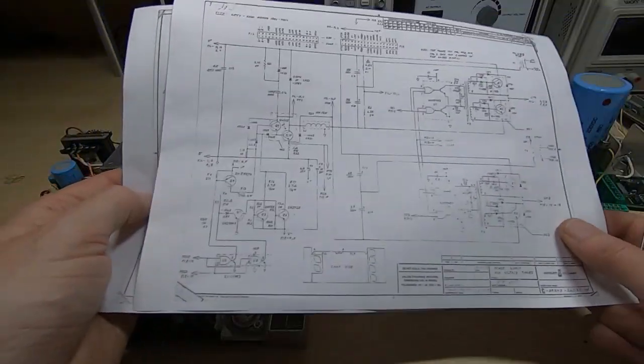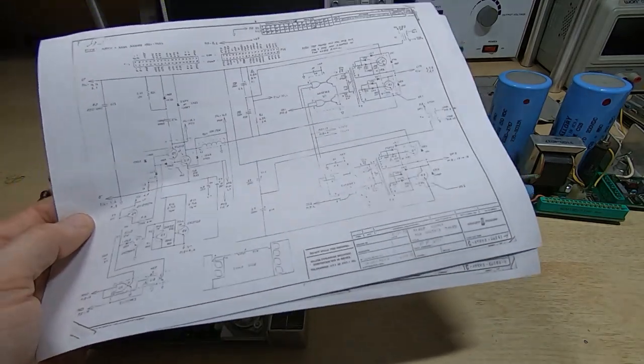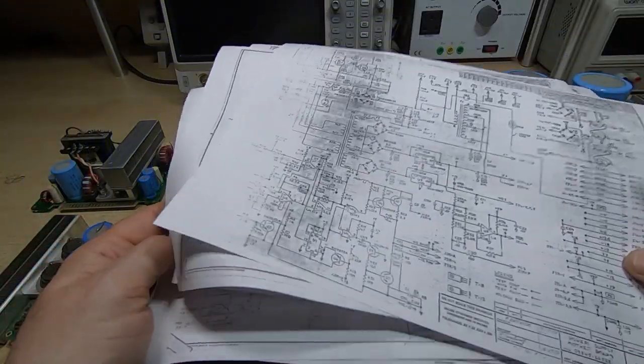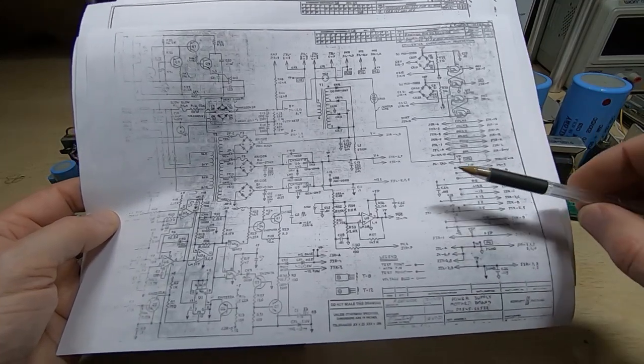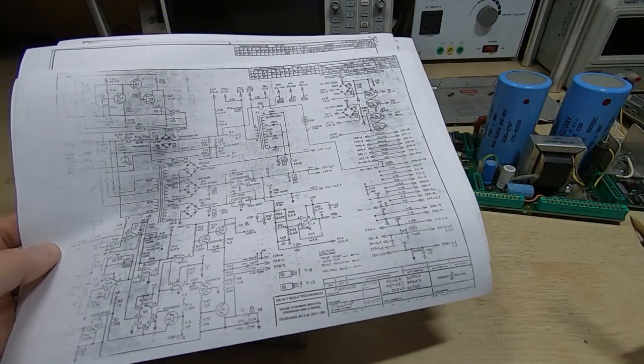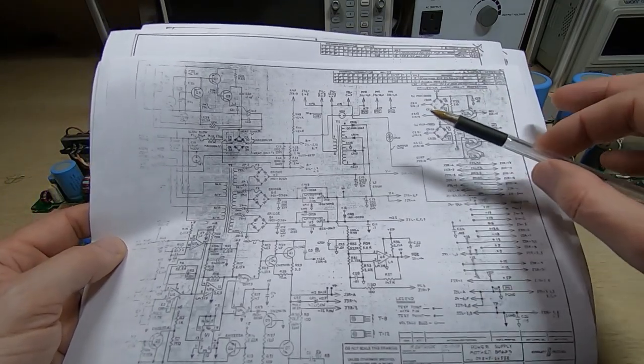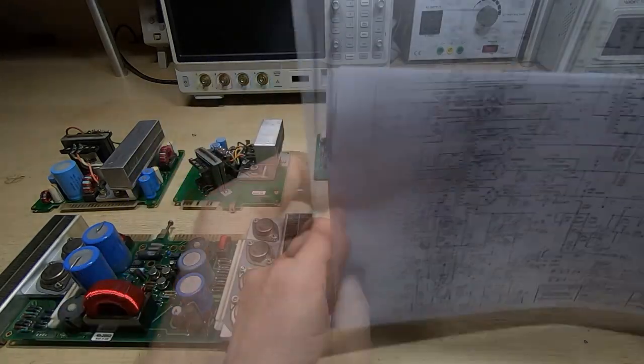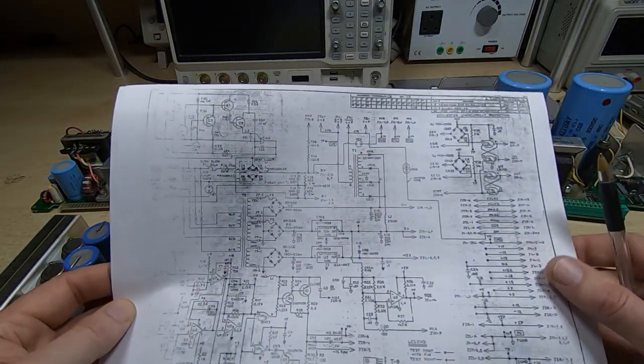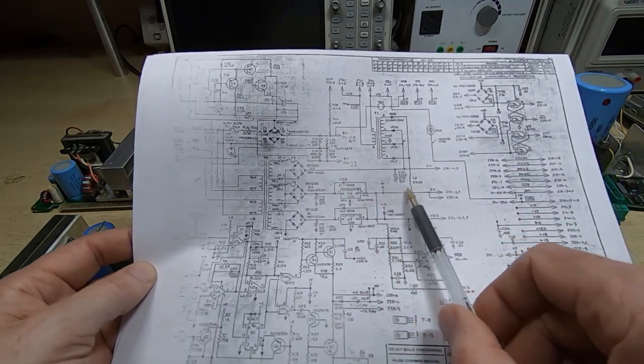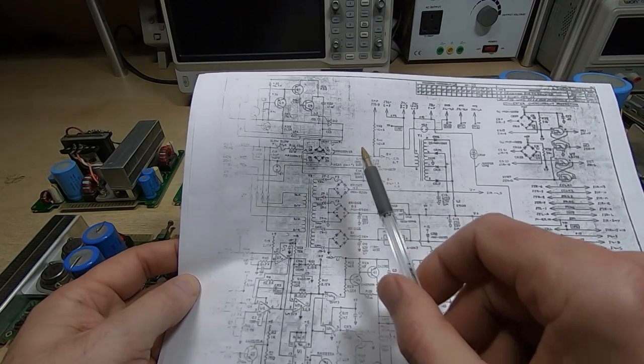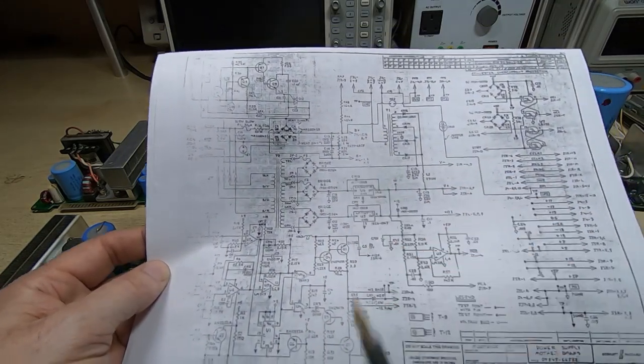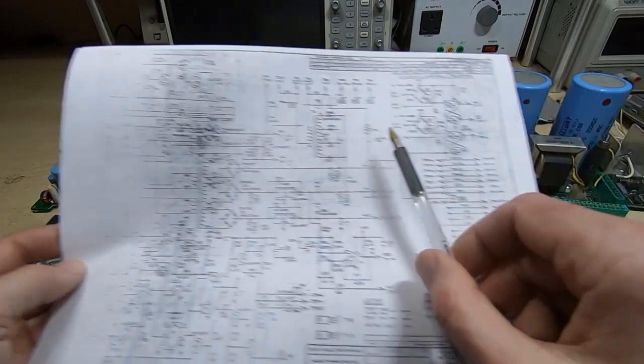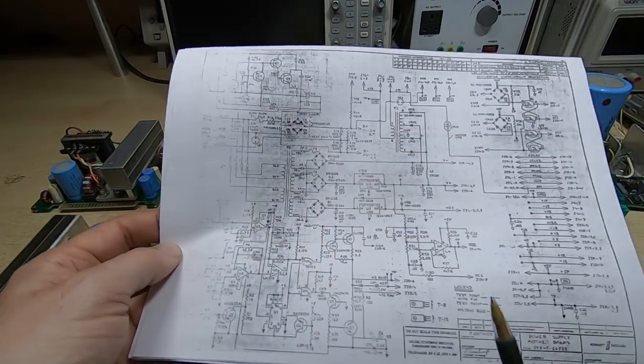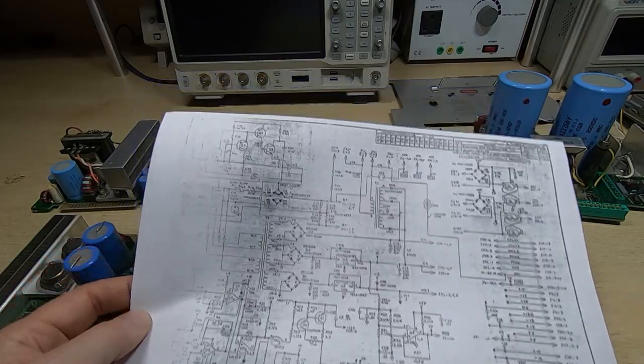So as you can see, it looks like a complex supply, but in reality it's relatively straightforward. We'll go back through this as we look into the supply and test it further, but we can test it in stages - we don't need to plug everything together to start with. We'll start with the motherboard, make sure we have our low voltage internal supplies, and also make sure we have the B plus and B minus supply. We'll test the soft start, and test the latches, making sure this all works the way it should before we plug anything else in.